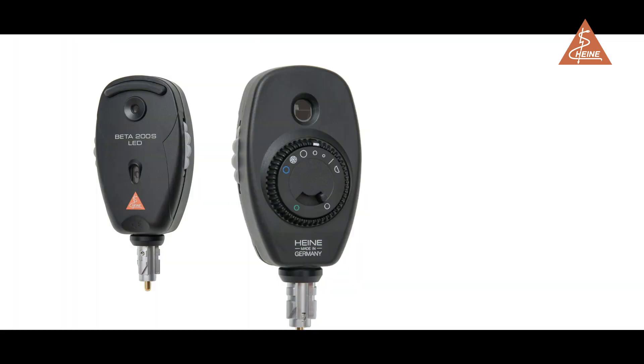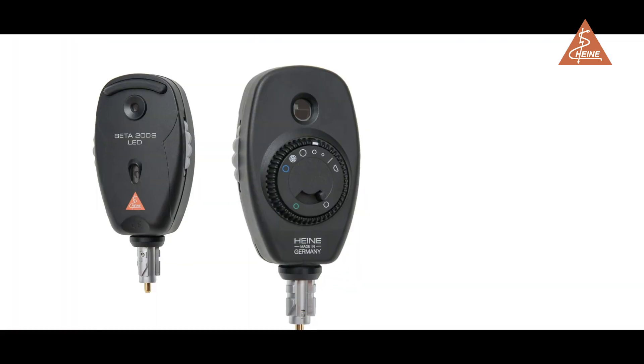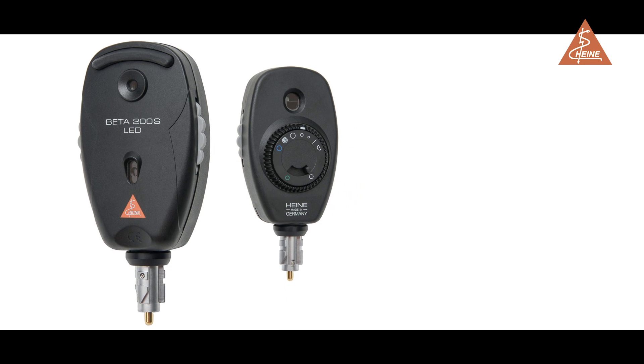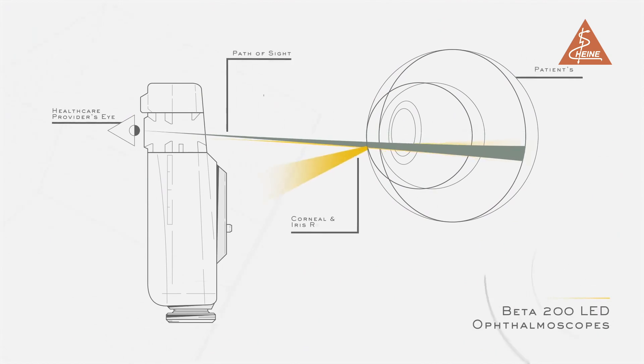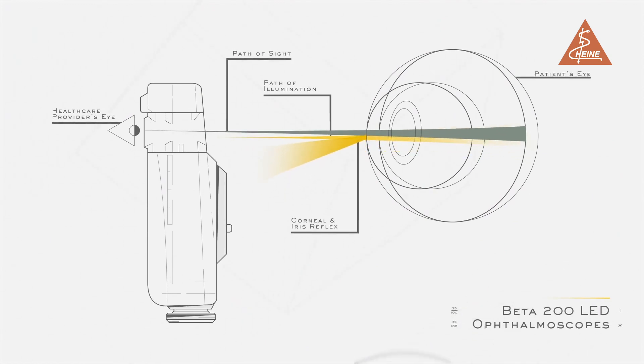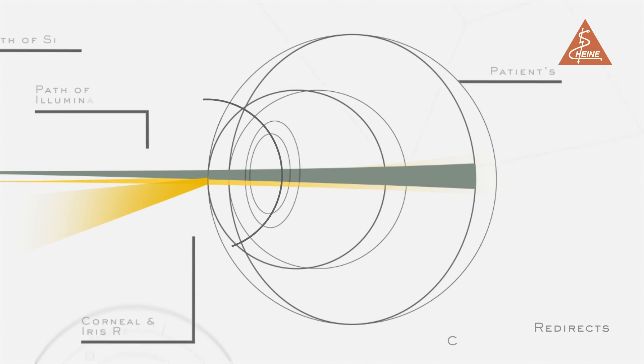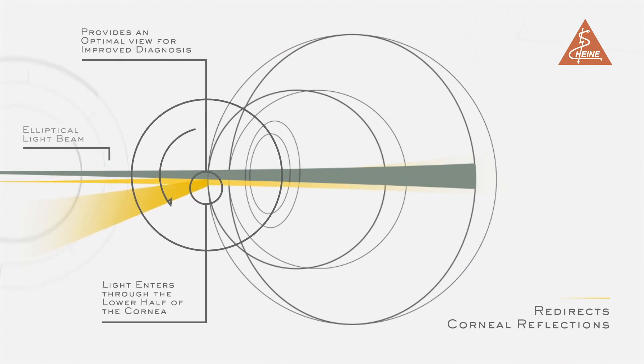One of the first things noticed when using the ophthalmoscope was the clear view of the posterior segment without reflection from the cornea. The team at Heine explained their secret: the AOS system. The ophthalmoscope cleverly separates the illumination and observation beams of light to eliminate anterior segment reflexes and allows for a crisp view of the posterior segment.